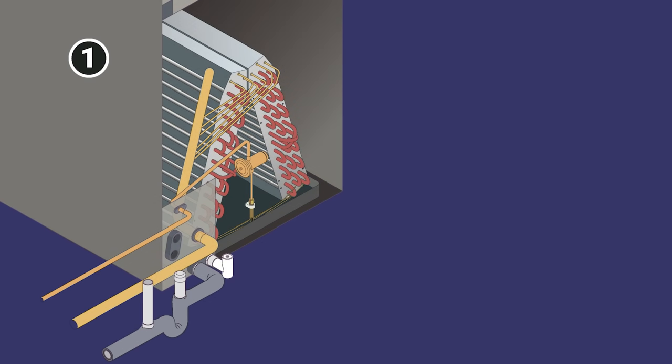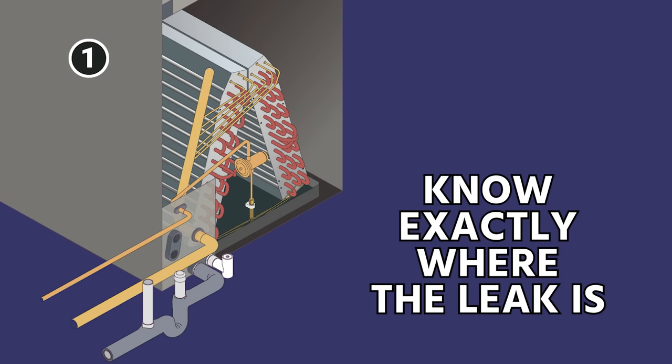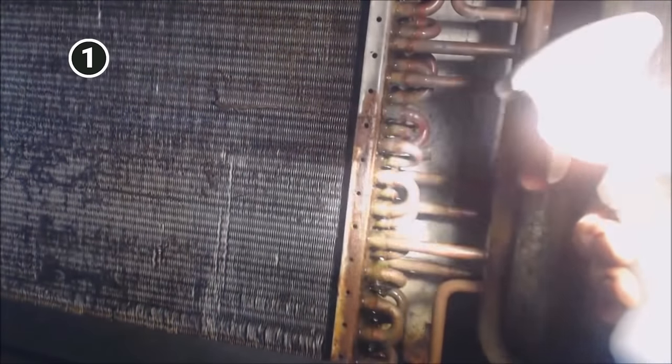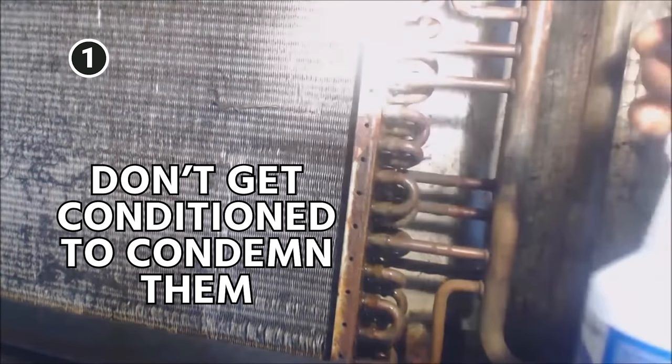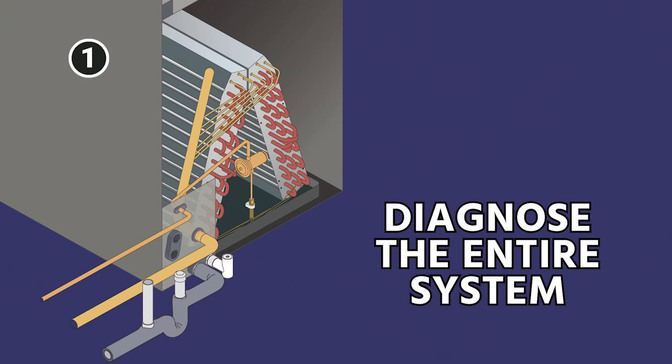The first step when you are going to replace an evaporator coil is to make sure that you know exactly where the leak is before you replace it. Because they have been so prone to leak in so many markets and in so many different systems, a lot of times technicians get so conditioned to condemning them that they don't diagnose the entire system.